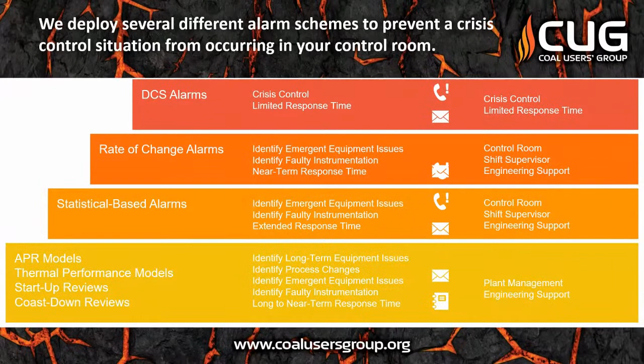By utilizing the modeling, the rate of change of alarms, statistical alarms, and fixed alarms, the POC is able to better determine operational issues before they reach a crisis point. Communicating these issues to the plant control room, sometimes in less than 20 minutes from when the change is detected, gives the plant additional response time to dispatch operators and take action, hopefully averting any type of crisis, equipment failure, derate, or plant trip.